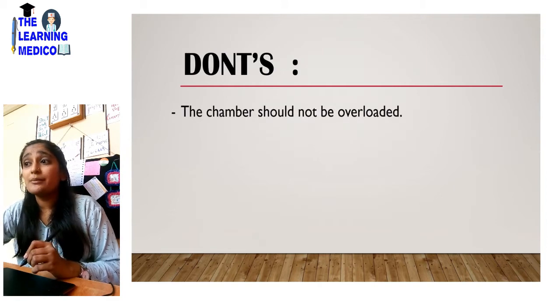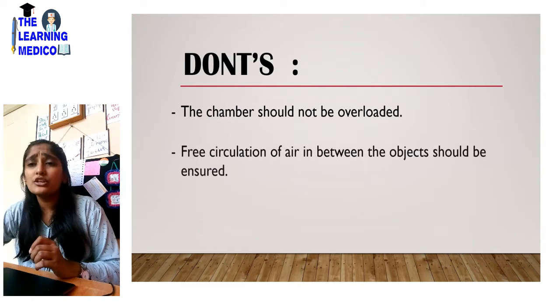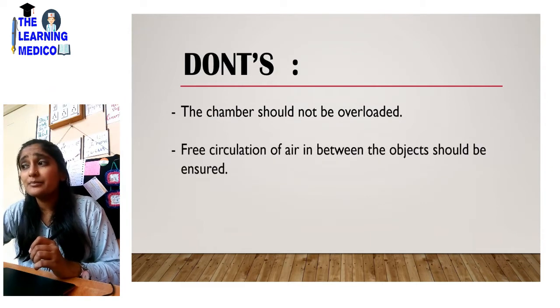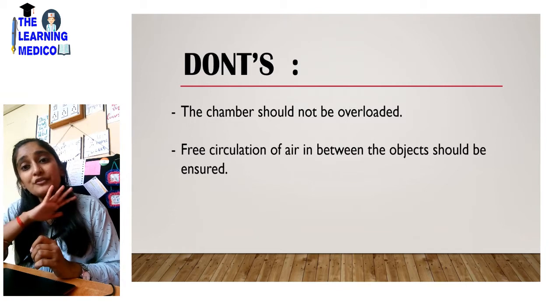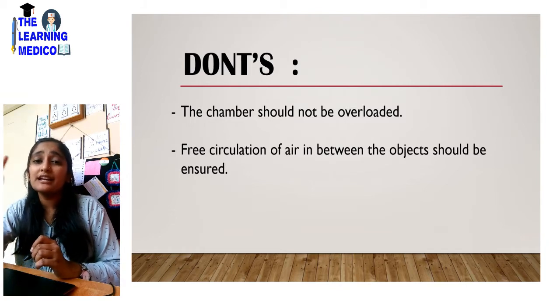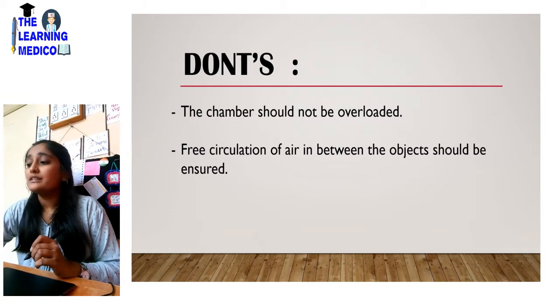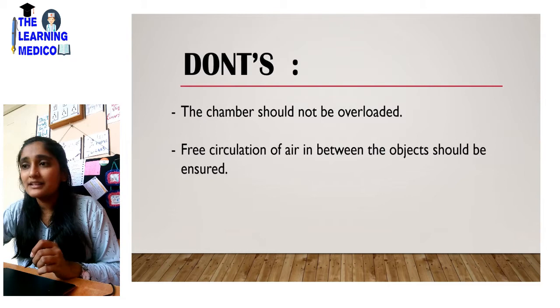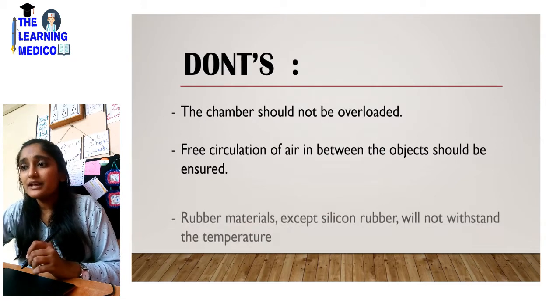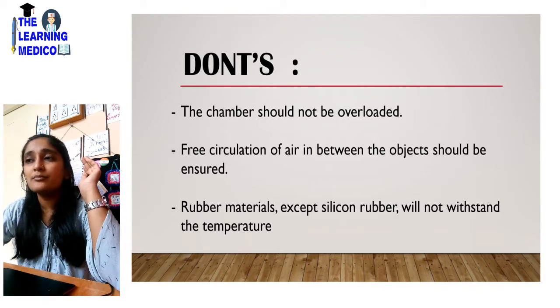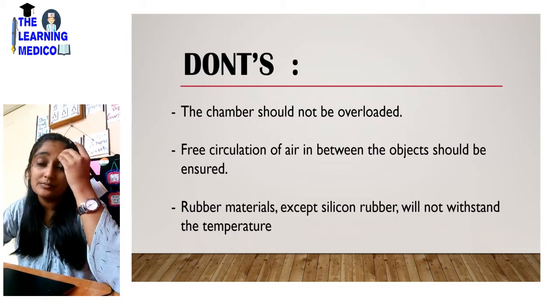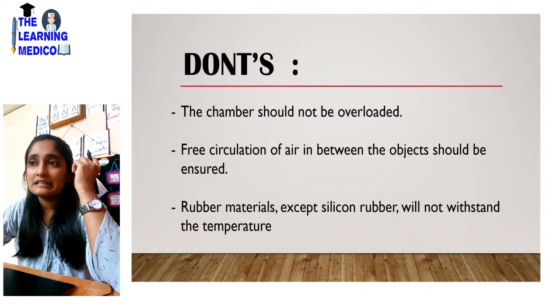What are the don'ts? The chamber should not be overloaded. Rubber materials — except silicone rubber — will not withstand the temperature, so rubber materials cannot be kept in the hot air oven.